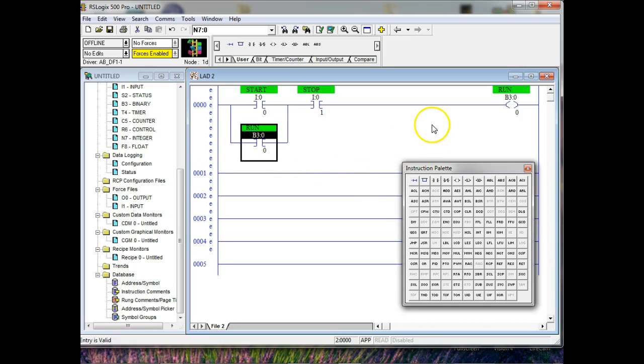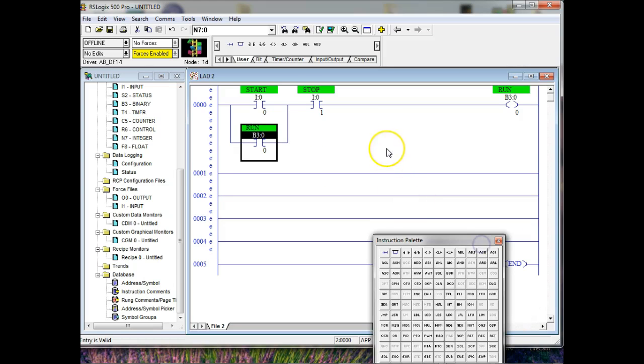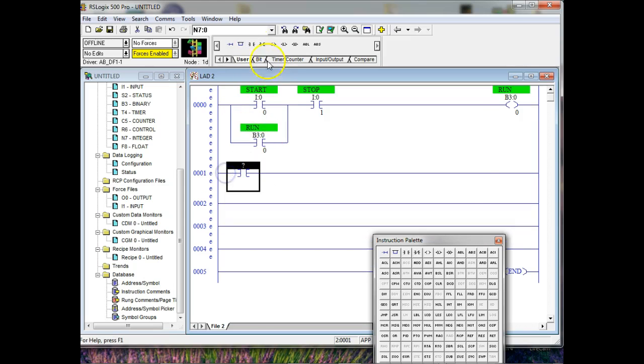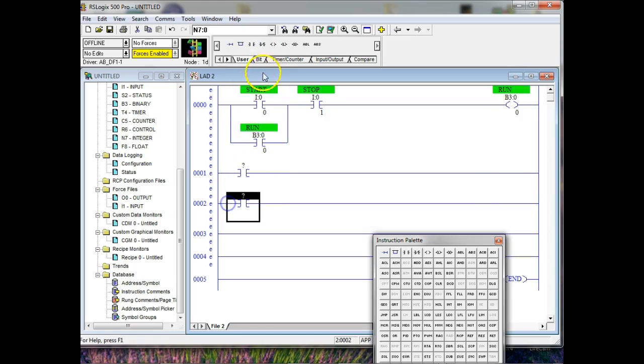So this is a standard start-stop station, right? Okay. And then what can we do with that? Now what you've got to understand, this guy here is supposed to stop everything. I had problems last time I taught it. They'd put this at the start, and it would mean nothing to the rest of the program. So how can we disable everything when I hit that? Well, one way we could do it is we could just put one of these in all our rungs, right?